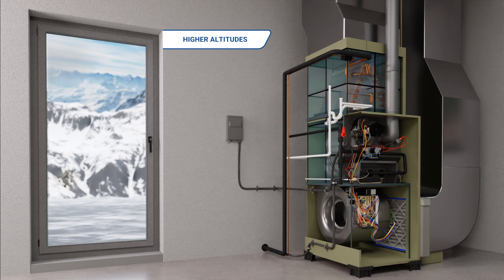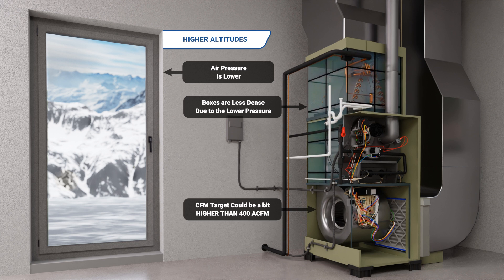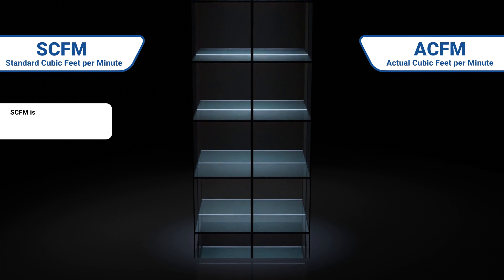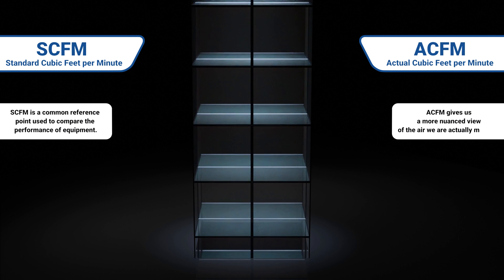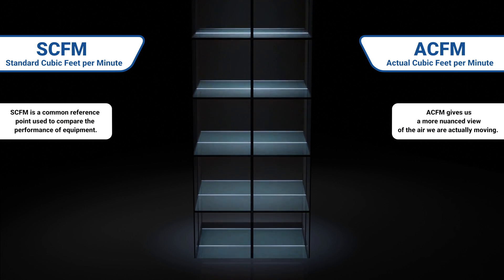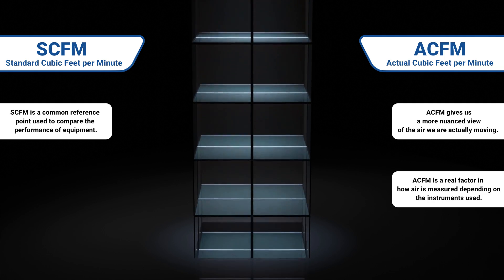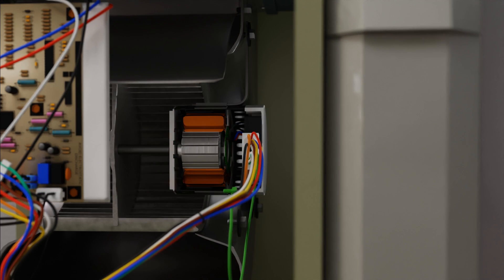These same concepts apply to air at higher altitudes. The boxes of air are less dense due to the lower pressure at high altitudes, so the ACFM will likely need to be higher at those upper altitudes due to the lighter air. It also makes a big difference what type of blower motor is in the equipment and how the weight of air impacts the blower's performance.